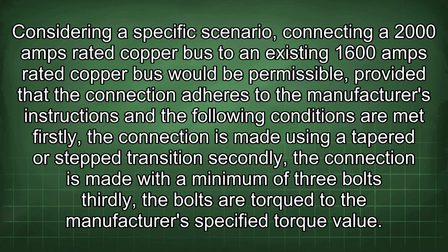Considering a specific scenario, connecting a 2000 amps rated copper bus to an existing 1600 amps rated copper bus would be permissible, provided that the connection adheres to the manufacturer's instructions and the following conditions are met. Firstly, the connection is made using a tapered or step transition. Secondly, the connection is made with a minimum of 3 bolts. Thirdly, the bolts are torqued to the manufacturer's specified torque value.